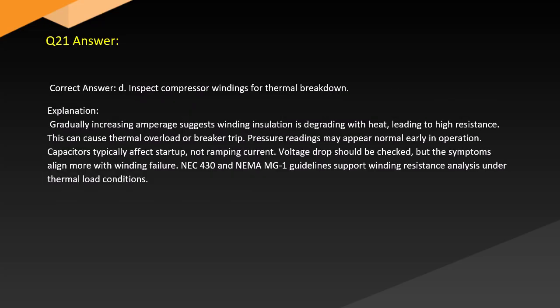Answer. Correct answer: D. Inspect compressor windings for thermal breakdown. Explanation. Gradually increasing amperage suggests winding insulation is degrading with heat, leading to high resistance. This can cause thermal overload or breaker trip. Pressure readings may appear normal early in operation. Capacitors typically affect startup, not ramping current. Voltage drop should be checked, but the symptoms align more with winding failure. NEC 430 and NEMA MG1 guidelines support winding resistance analysis under thermal load conditions.